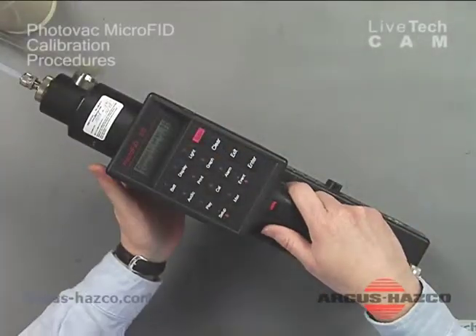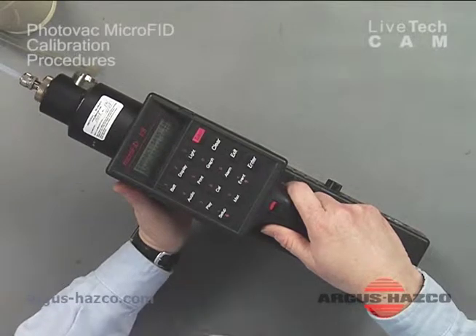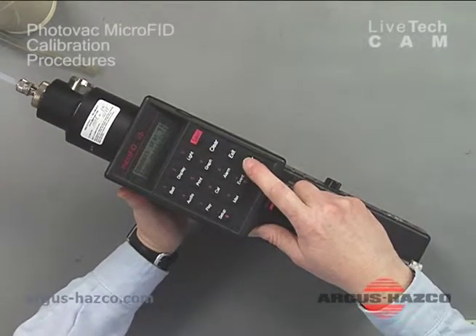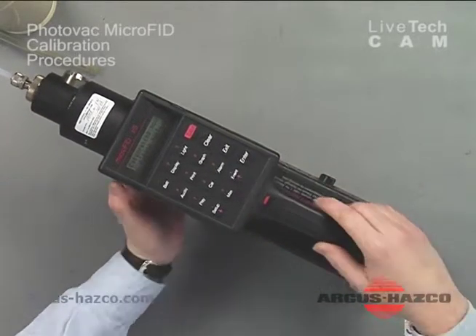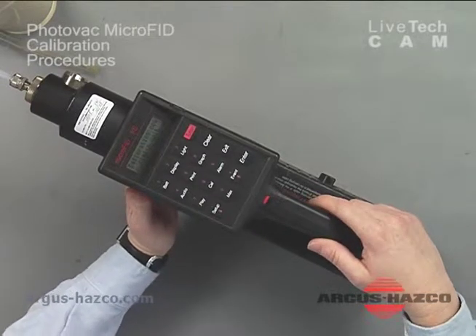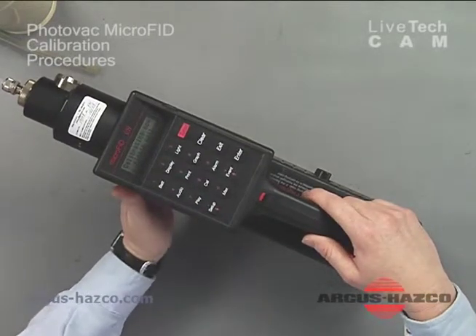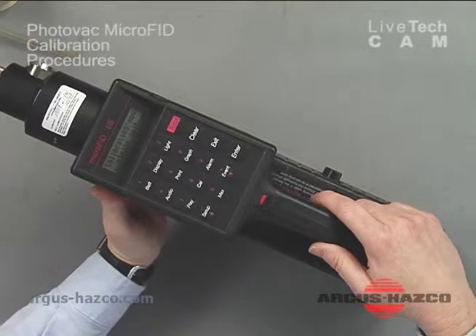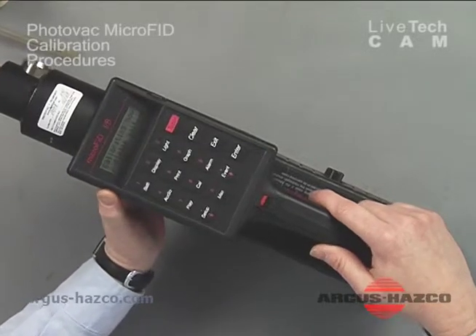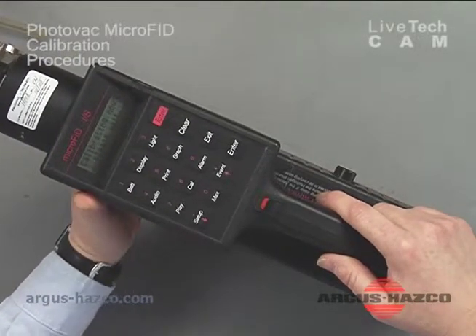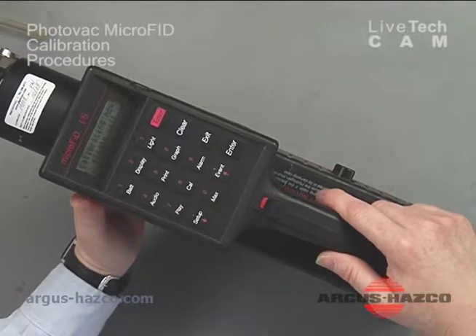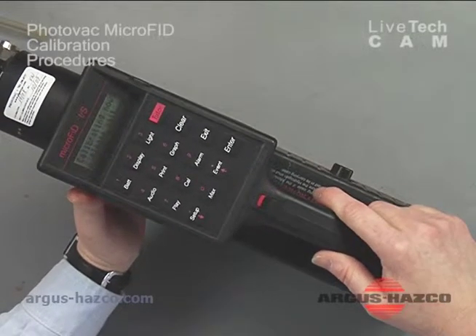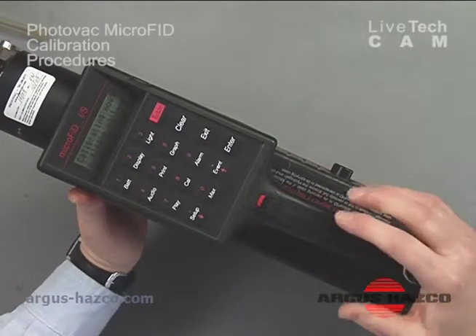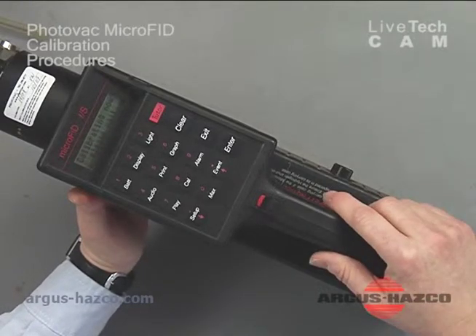Here it says connect span gas, then press enter. So we press our enter key again. And our unit's back to calibrating now, please wait. This operation, if you noticed on the zero air, took a few minutes to calibrate, and it'll do the same thing with our 100 ppm methane span concentration. And when this unit is done calibrating, it's just going to go right back to the normal reading mode.